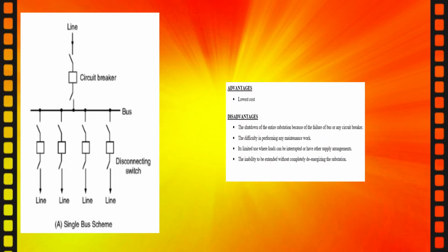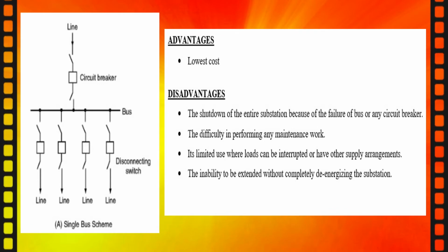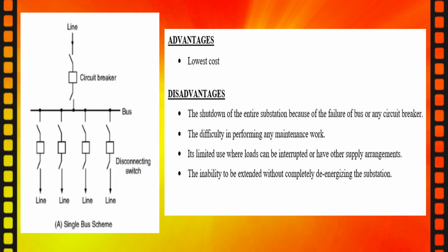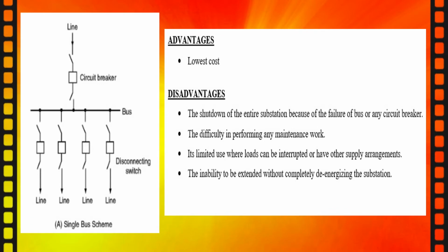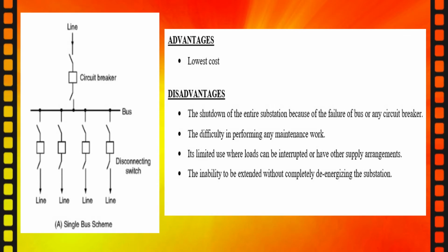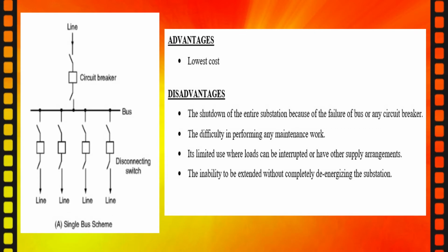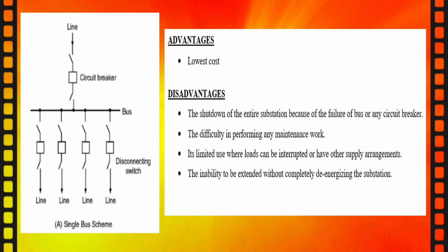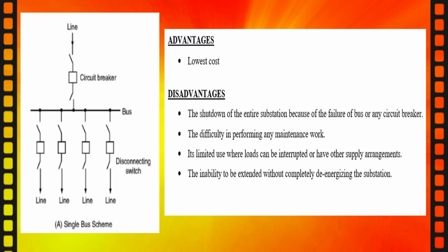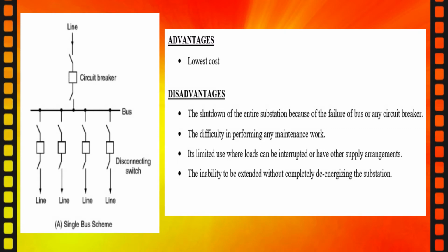The advantage of single bus is lower cost. The disadvantages are the shutdown of the entire substation because of the failure of the bus or any circuit breaker. Second, the difficulty in performing any maintenance work. Then it is also of limited use where load can be interrupted or has other supply arrangements.